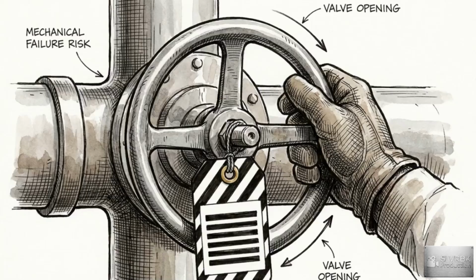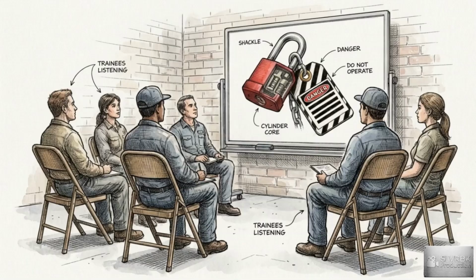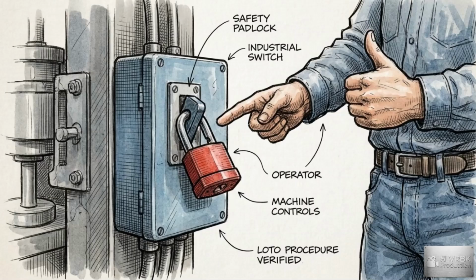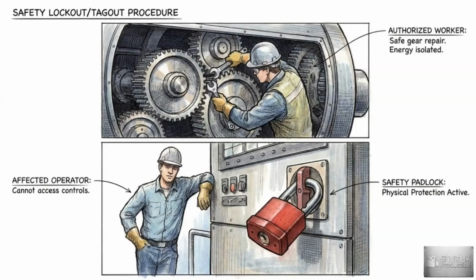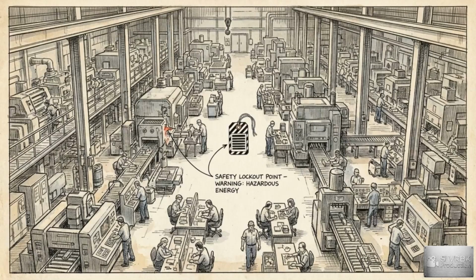Failing to read a tag out of habit, they can easily turn a valve and energize the system while someone is inside. For this reason, affected employees are required to undergo specific training, simply to recognize when energy control procedures are active and to understand why they must not intervene. A physical lock actively protects both the authorized worker inside the machine and the affected operator outside of it. Tagout demands perfect, continuous behavioral compliance from every person in the building.